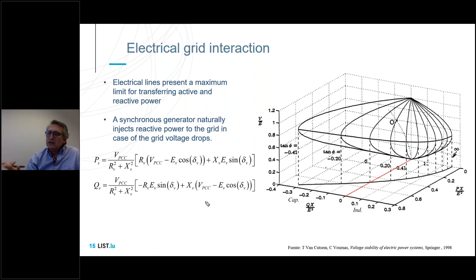The power converter is able to generate a given switch voltage that, once interacting with the grid, will produce a current with a little ripple due to the effect of the filters. So in principle, we could understand this voltage source converter as a voltage source, which determines the voltage at the point of connection, but it can also be controlled to determine the value of the current injected into the grid.